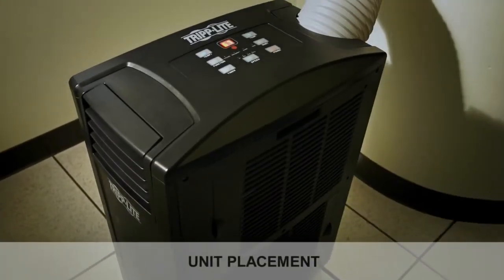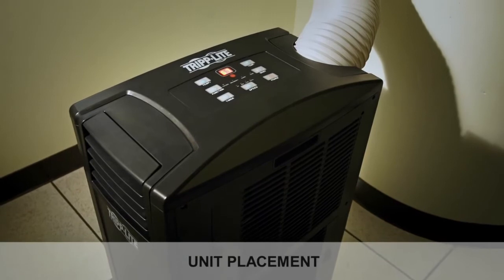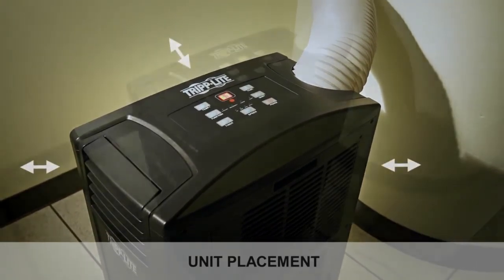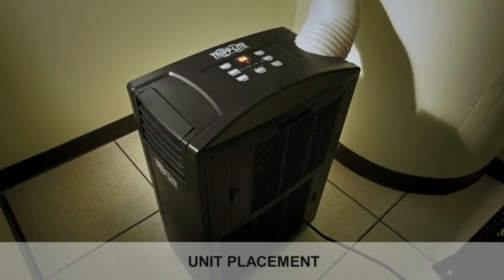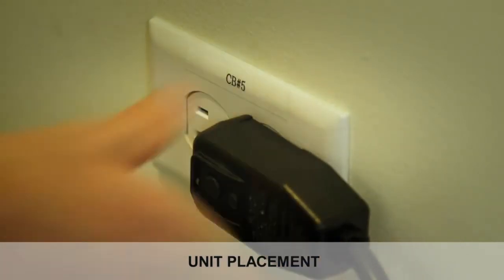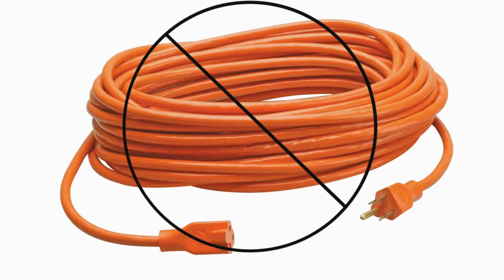Prior to installation, ensure that the unit will be located in a level space with at least 20 inches clearance on all sides for proper airflow. The unit should be installed in a location close enough to an AC power outlet to allow you to plug the unit in without straining its cord. Do not use an extension cord to connect the unit to AC power.